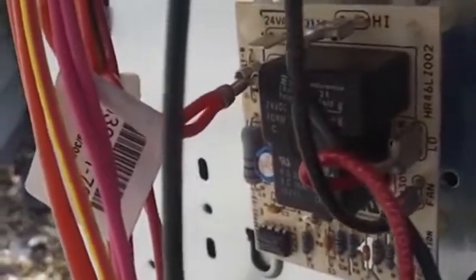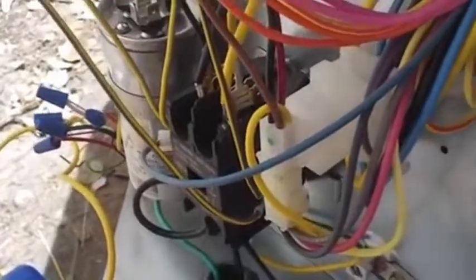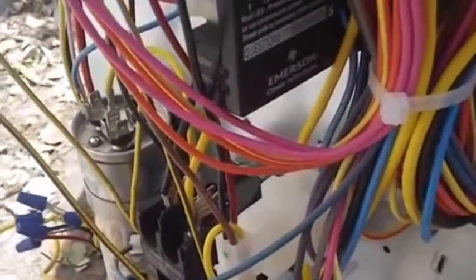Another shot of some of the controls here. What you do on the Heil is you unplug the yellow and brown fan wire going to the 24 volts AC terminal up top. That means the fan will run in high speed constantly. That's what we want when we're charging, so we get a proper subcooling, because if the fan slows down, subcooling goes down too and gives you a false reading.